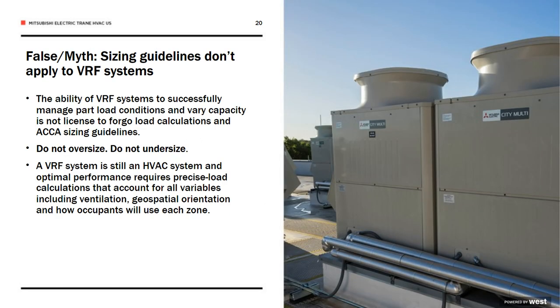All right, so a myth. Sizing guidelines don't apply to VRF systems. Sometimes people will think, well, with VRF, since it's variable and it can speed up and slow down, I'm going to just grossly oversize this and put that system in. Well, that is not a good idea.